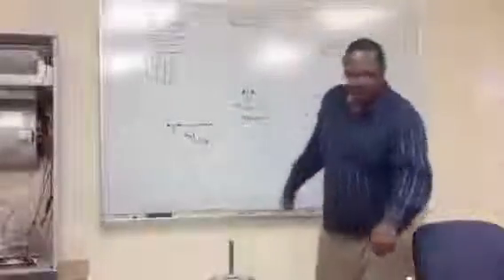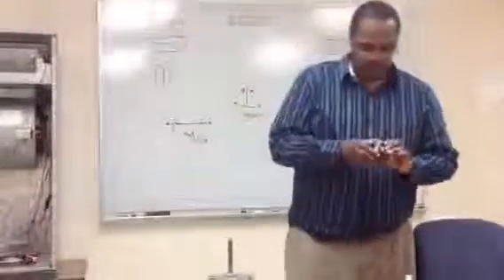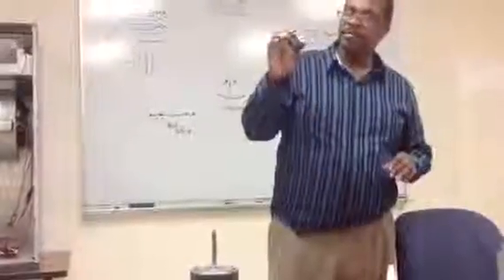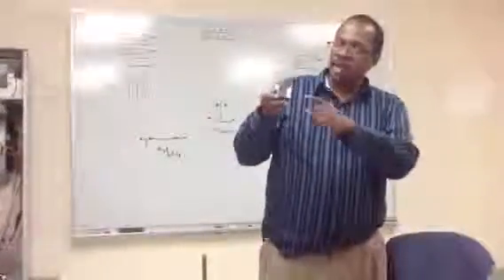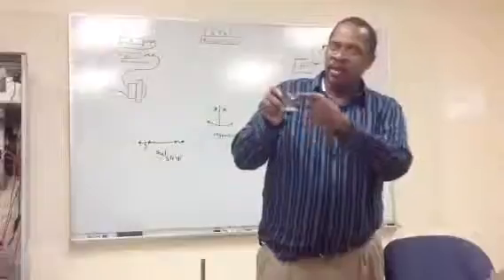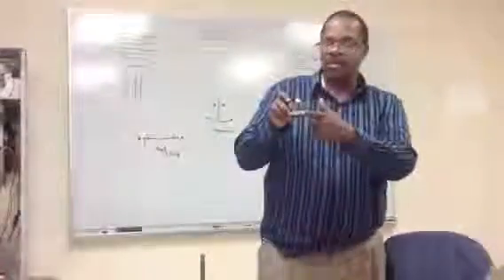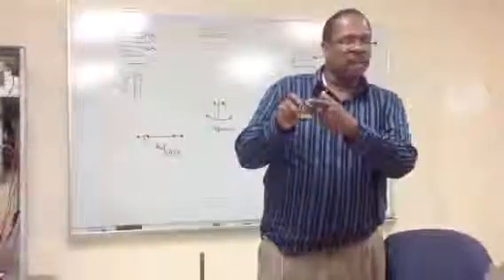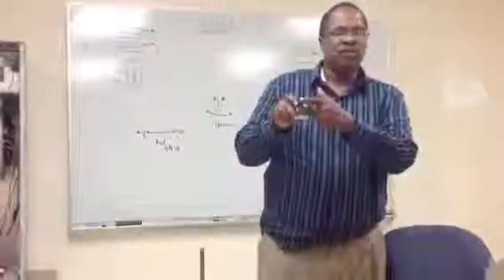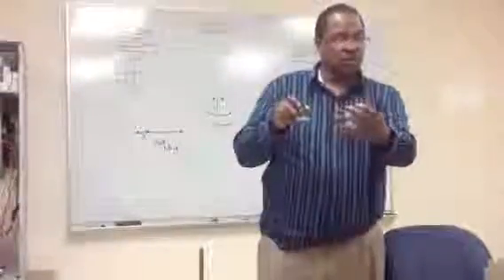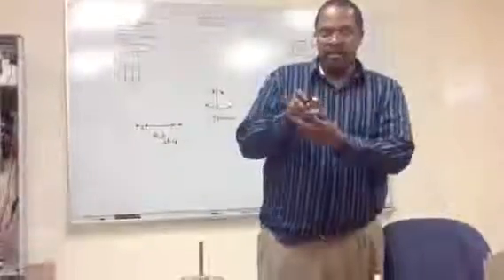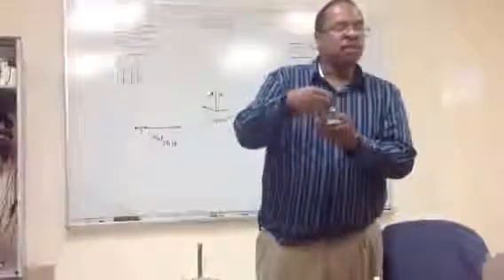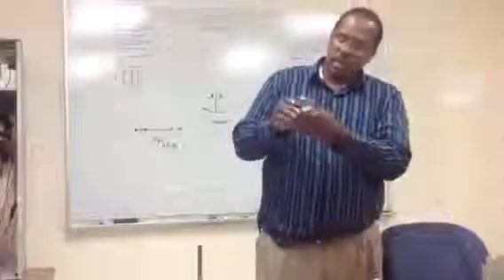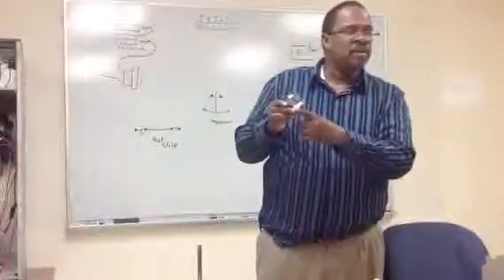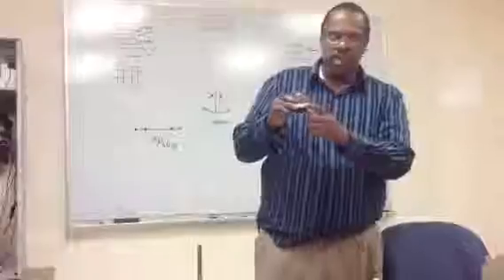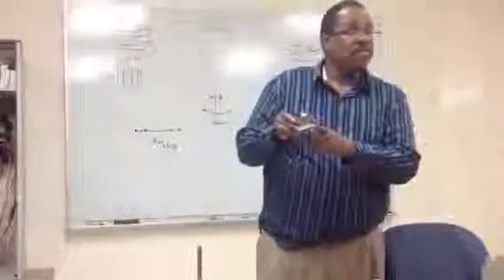Now, here is a transformer. It's a little taped up, still good. But you'll notice it has 3 connections on one end and 2 on the other. These are different taps. The 2 taps, if you read inside the transformer, are usually your 24 volts. Some will have wires coming off that you hook up to. Some will have male connectors that you plug a female connector over. On the bottom, we have a common, we have our 208 tap, and we have our 240 tap.